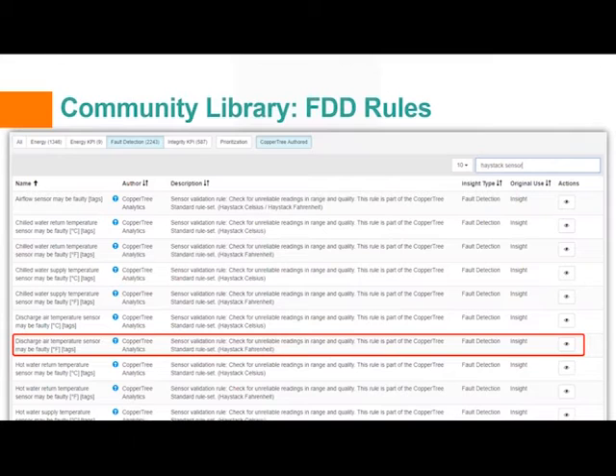Highlighted here in red is a sample rule. Discharge air temperature sensor may be faulty. You can see the unit, it's degree Fahrenheit, and it's using haystack tags. The description says sensor validation rule, check for unreliable readings in range and quality. This rule is part of the CopperTree standard rule set.